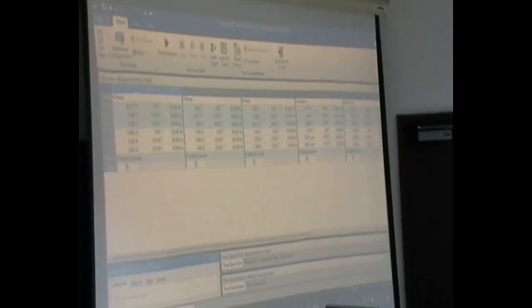These files we've already made, otherwise it needs some configuration for whatever measurement you want to make, what current you want to inject, and I'll go through the timing and other tests later on. Again, the Omicron will give us some ready-made template for the testing, which is very, very useful. I'll start the testing. In the tables, you could record only the normal measurement, which is first injection in 63.5 volts. I'll start it, then you can read from the relay. So we're starting the test.